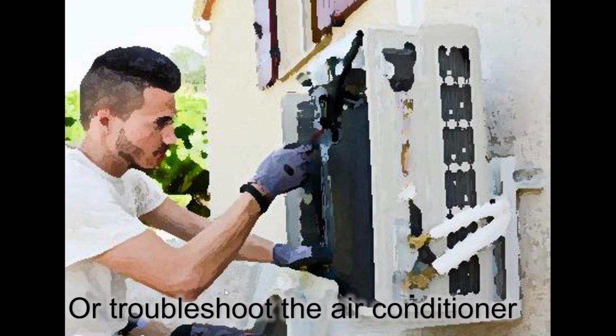This is general basic practice when you're installing the unit. Don't install the outdoor unit like 20 feet in the air. Keep it at a good height so that this guy can install it, this guy can troubleshoot it, without worrying about somebody to hold my ladder or from falling down. So please, guys, bring that pipe down, cover it in a slim duct, make it look neat, make it look nice, make it look clean. Put the unit just above the ground.